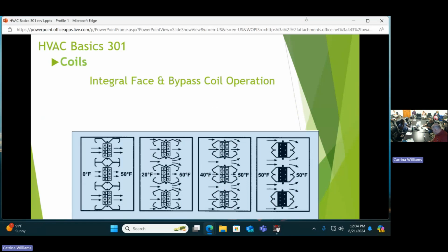Now then, the way this works is at 0 degrees, as cold as, that's their design point, all the air is going through the fin tubes, and the bypass is totally closed. So as outside air warms up a little bit and you get up to 20 degrees, now you're modulating airflow between the fin tubes and the bypass to get the 50 degrees that you're looking for downstream.